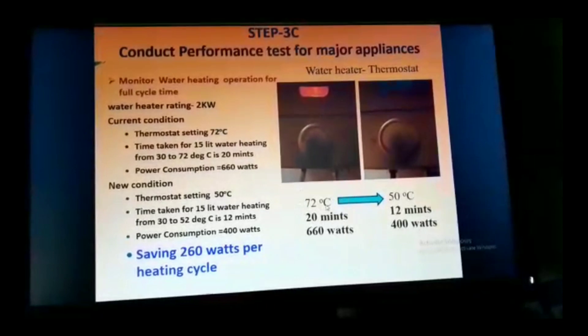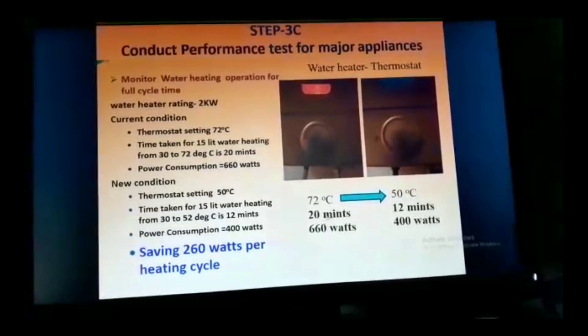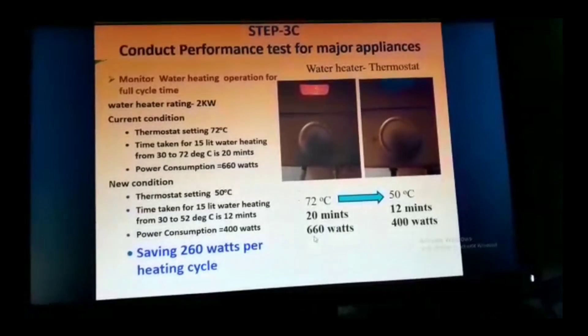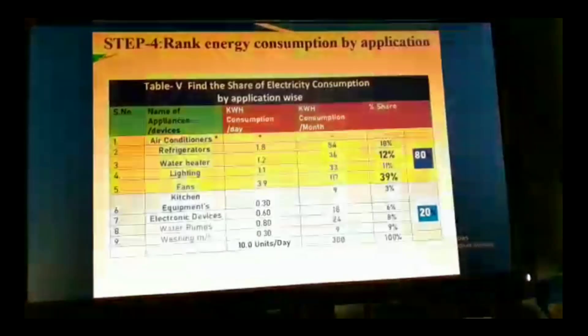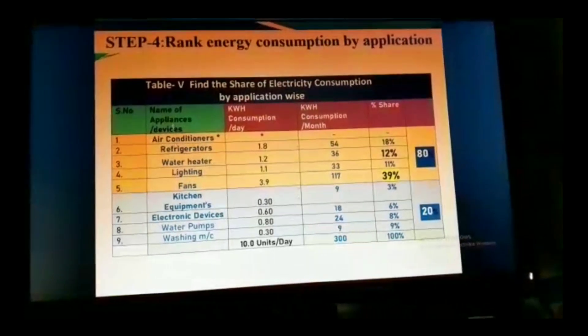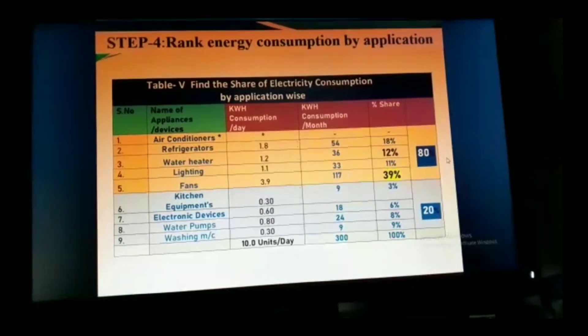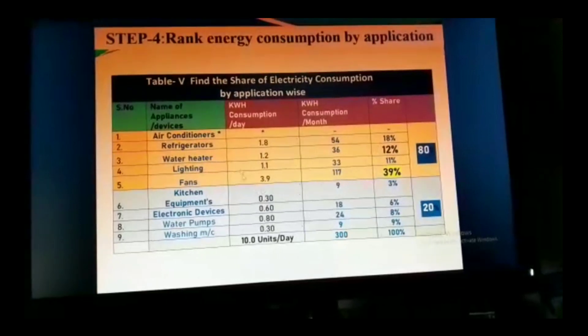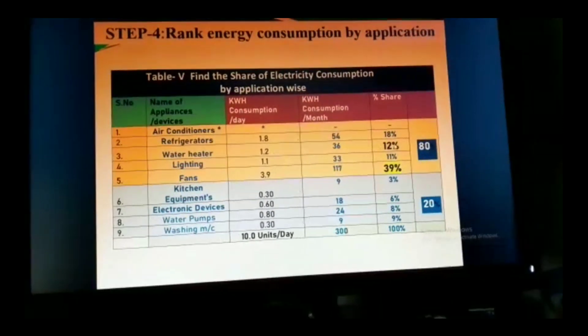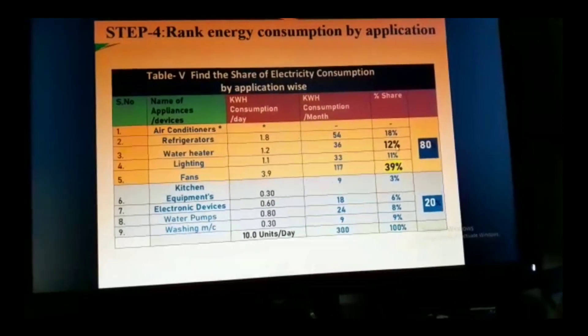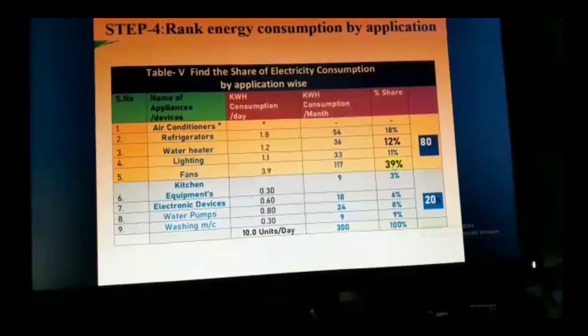Performance testing can also be conducted on pumps and water heaters. For example, the thermostat was kept at 72°C — during the energy audit it was found to be too high and was reduced to 50°C, reducing cycle time and energy consumption by about 260 watts per heating cycle. After collecting all information, calculate, summarize, and rank it. Out of nine appliances, the top five consume 80% of energy. Among those, lighting alone consumes almost 40% and the water heater 12%. The 12% can be eliminated by installing a solar water heater, and fans can be replaced with BLDC fans to reduce consumption by 50%.